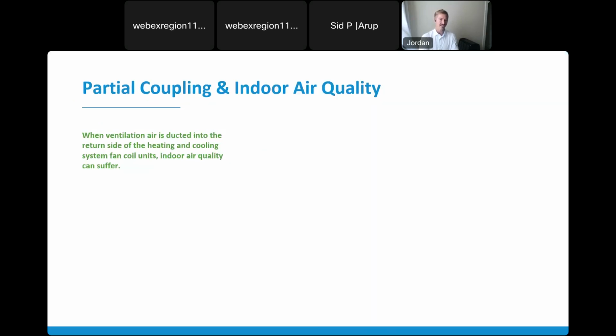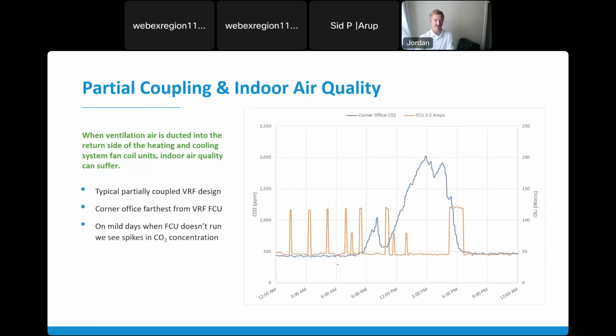One example of that is we've had a couple of demonstration projects, not included in those 14, but research studies where we've had partial coupling. So ventilation air delivered to the return side is a very common strategy, especially in Oregon and other states outside of Washington. They do this because you don't need nearly as high ventilation or heat recovery effectiveness, or you don't need as much post conditioning if you have a heating or cooling coil on your DOAS units. But this can cause some significant issues, and we've proven this in a few different projects where indoor air quality suffered. Here's an example of that.